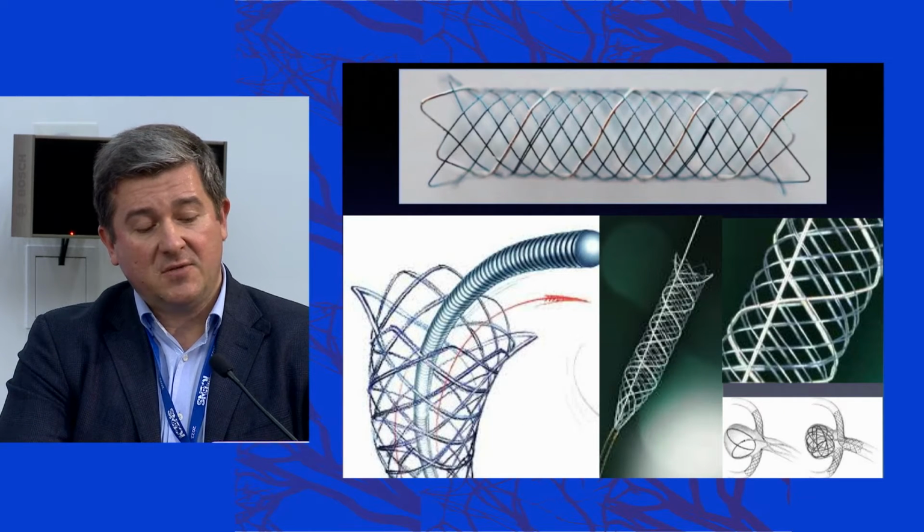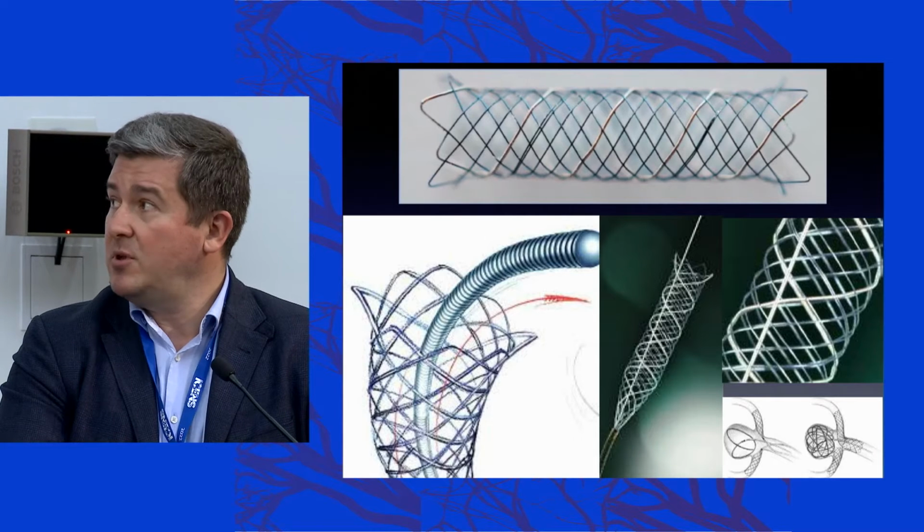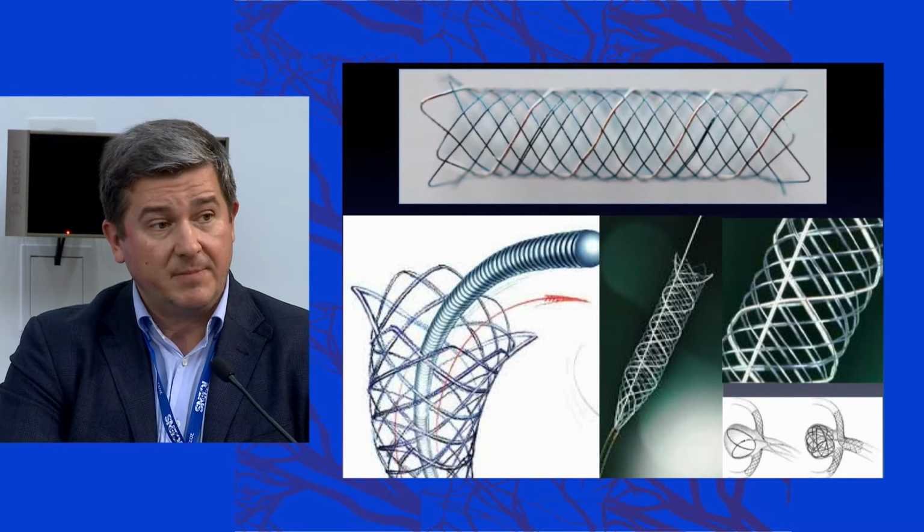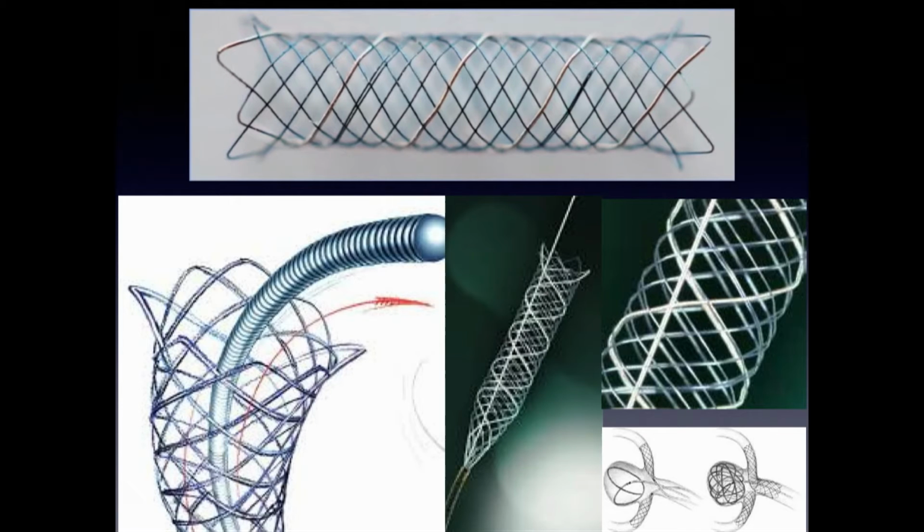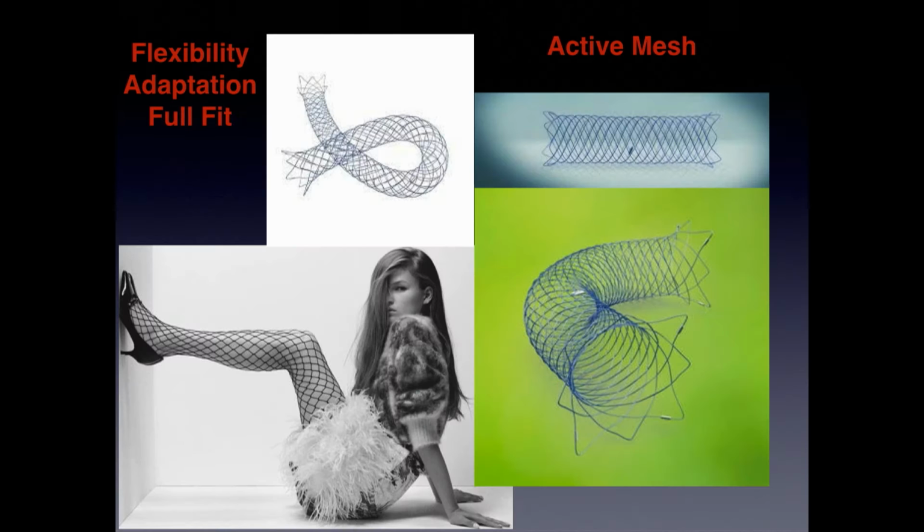Look here. Braided low-profile stents look very different. First of all, there are no crowns, no extended markers that hampered work with classic stenting. Another important point is the particular flexibility, and how it is achieved.